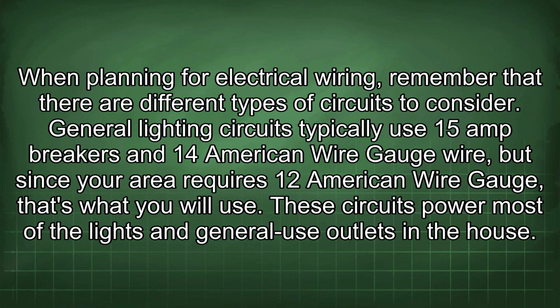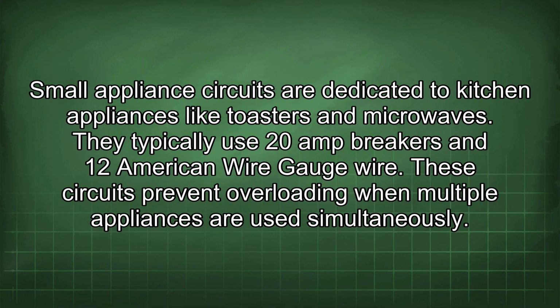When planning for electrical wiring, remember that there are different types of circuits to consider. General lighting circuits typically use 15 amp breakers and 14 American wire gauge wire, but since your area requires 12 American wire gauge, that's what you will use. These circuits power most of the light and general use outlets in the house. Small appliance circuits are dedicated to kitchen appliances like toasters and microwaves. They typically use 20 amp breakers and 12 American wire gauge wire. These circuits prevent overloading when multiple appliances are used simultaneously.